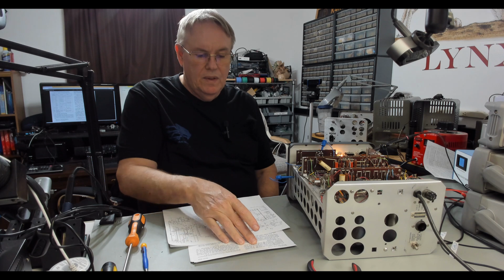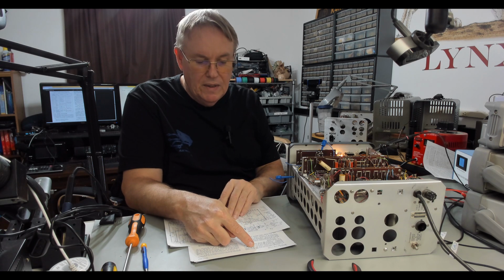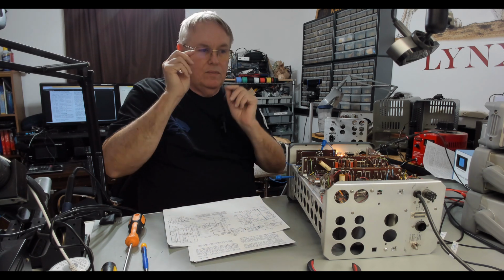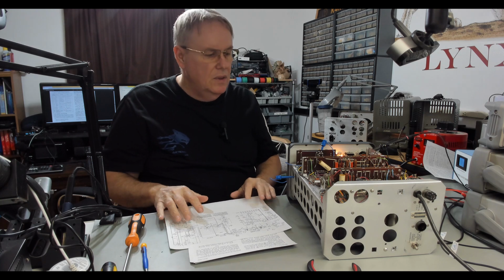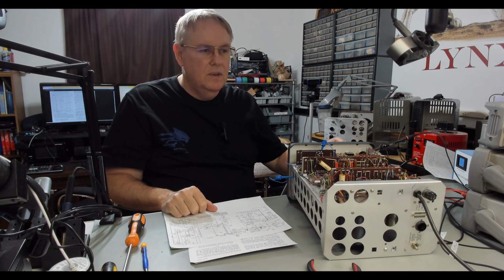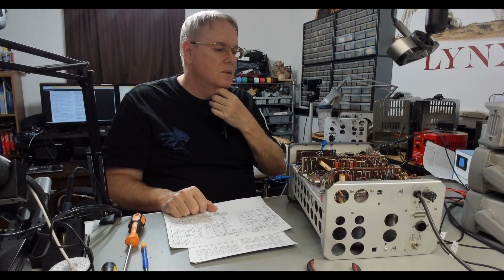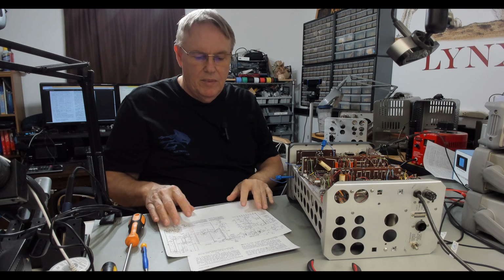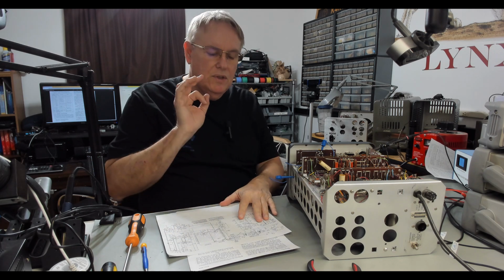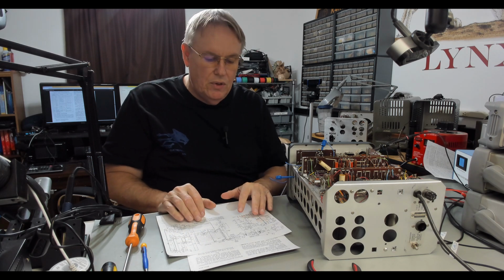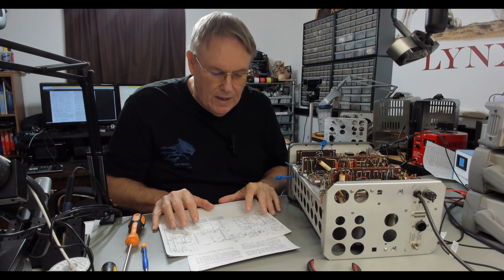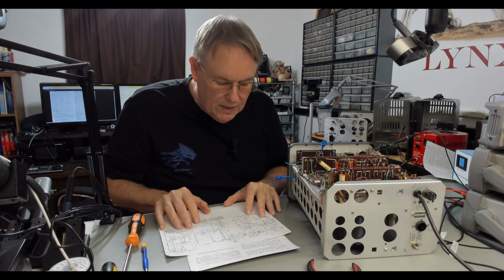So see, 2 is if the signal at test point is not correct, check V7. Okay, so V7. So V7 is what I need to be looking at, it says. So I can recheck V7. Kill this. I can do that. Let me recheck V7, make sure it's reading good on the tube tester, and then we'll start looking around that area for anything that might be causing this problem.